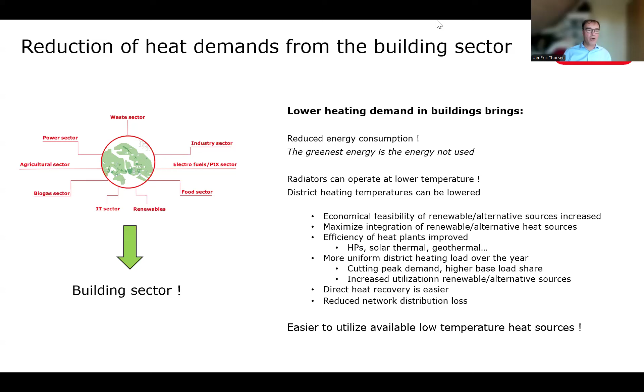And we did different things. So many traditional existing buildings have heating systems based on boilers, gas, oil, where temperatures traditionally were not so critical. So here we changed from a one-pipe system to a two-pipe system. Individual thermal control by radiator thermostatic valves. We made a very careful balancing of the system so that all the radiators are evenly utilized, and that actually gave a 5% energy saving. Next step was insulation on the attic. That gave 3%.